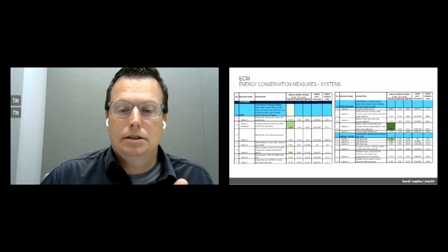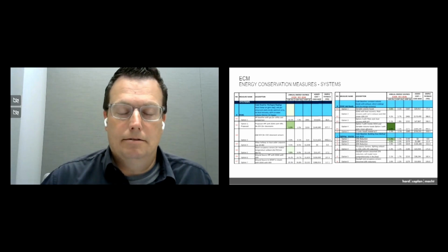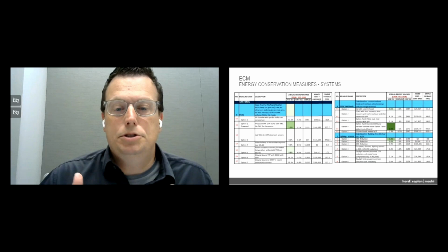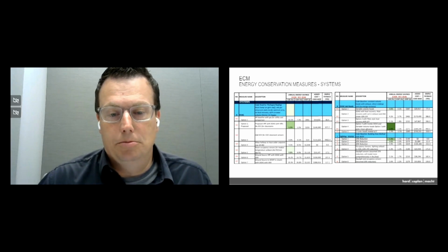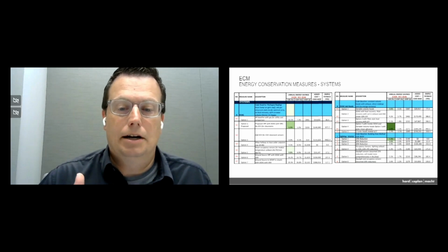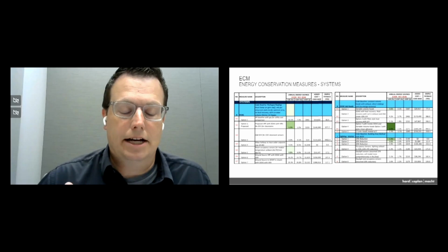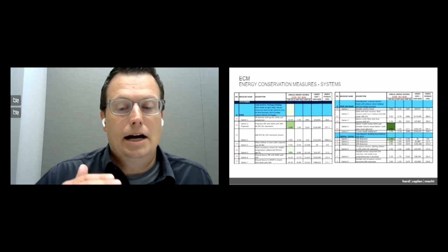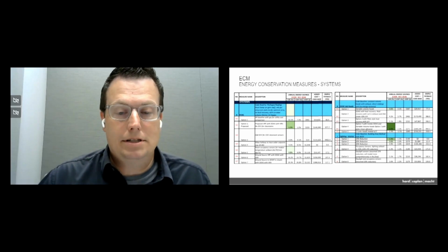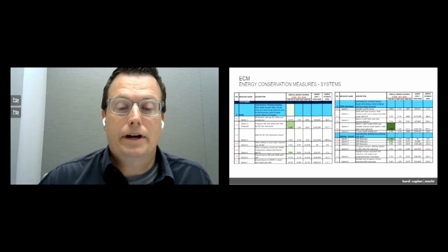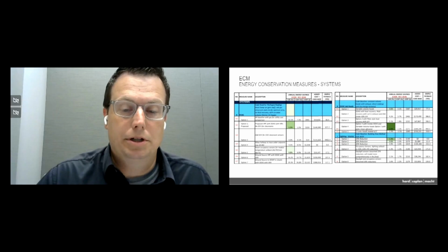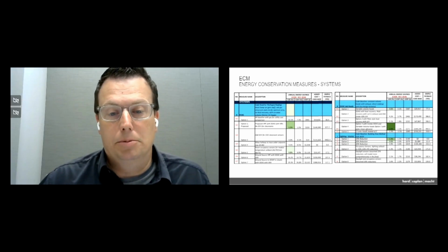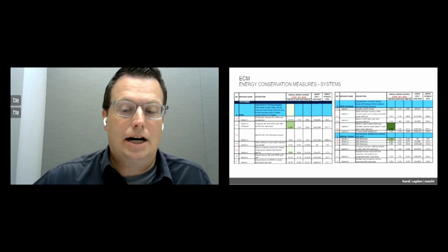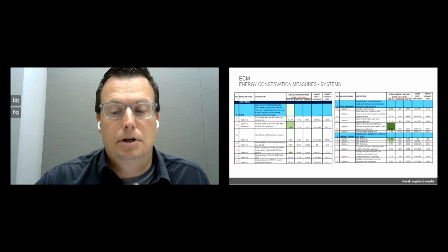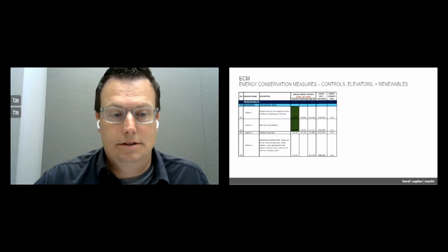We went from a constant volume of air exchange to a variable volume that allowed the fume hood to kick on and off as it was actually in use during class. That set up a considerable amount of savings from an efficiency standpoint, driven by the operational use pattern, and using variable volume air instead of constant air produced a large amount of our overall savings.